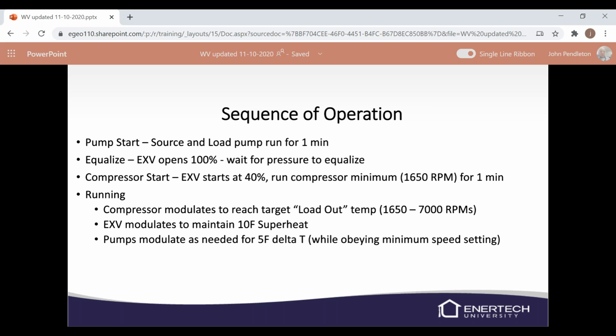So if for some reason maybe you don't have the domestic water hooked up yet, or you don't have the load hooked up yet, vice versa, you could run it in whatever mode is piped in and ready to go, and then come back later and put the tank in or whatever and go through that setup again and flex that valve and flush the circuit and then run the unit. So that just gives you an option to be able to do that.